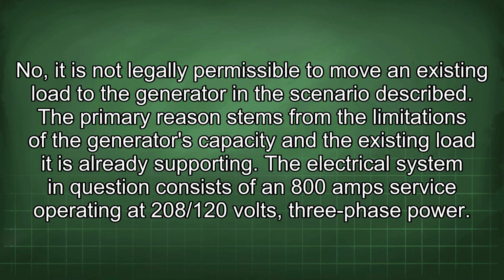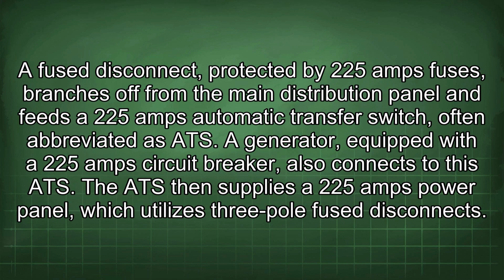208/120 volts, 3-phase power. A fused disconnect protected by 225 amps fuses branches off from the main distribution panel and feeds a 225 amps automatic transfer switch, often abbreviated as ATS. A generator equipped with a 225 amp circuit breaker also connects to this ATS. The ATS then supplies a 225 amps power panel, which utilizes 3-pole fused disconnects.